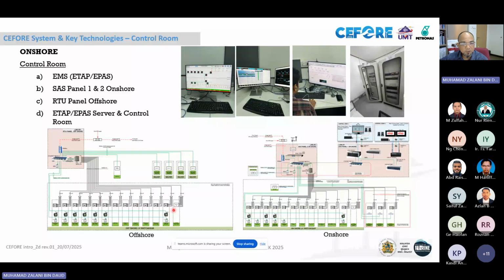From offshore, we collect all the data from the DPMs using TCP/IP communication, Modbus TCP/IP, and we have point-to-point communication from the RTU panel to the breakers to collect data and control the circuit breakers offshore. This instrumentation is connected to onshore using fiber optic.